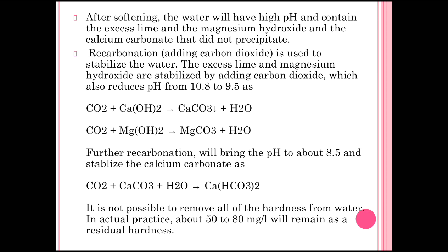When CO₂ reacts with magnesium hydroxide it forms magnesium carbonate, but since magnesium carbonate is easily dissolved in water, more lime is added to remove it. The pH for this reaction is maintained at about 8.5 to stabilize. When CO₂ reacts with calcium carbonate in the presence of water, it gives calcium bicarbonate. It is not possible to remove all the hardness from water, so actually about 50 to 80 mg/L will remain as residual hardness.